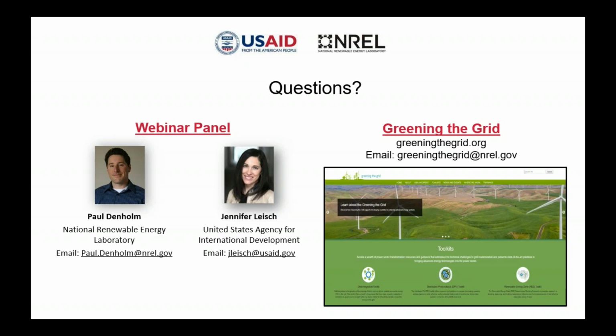Not yet, it's pretty immature. What we do know is that the relative power capacity of the storage is typically going to be a lot less. I wouldn't want to state a firm rule of thumb, but for the optimum mix, it's not going to be 1-to-1. If you've got 100 megawatts of PV, it's not going to be 100 megawatts of batteries—probably 20 or 30 megawatts, to take advantage of the inverter without overloading the power components of the system.